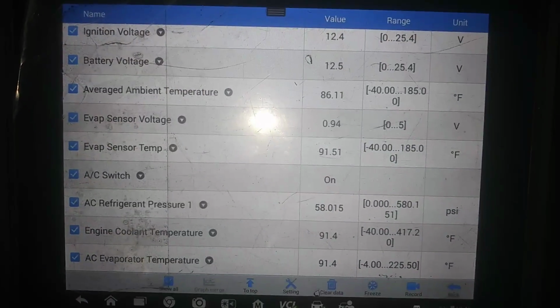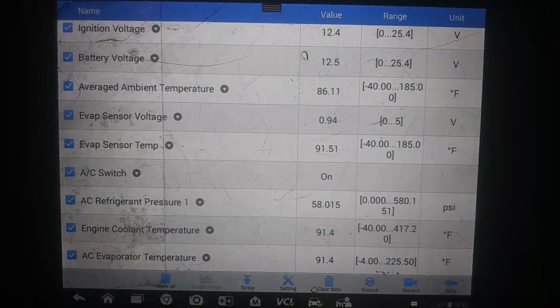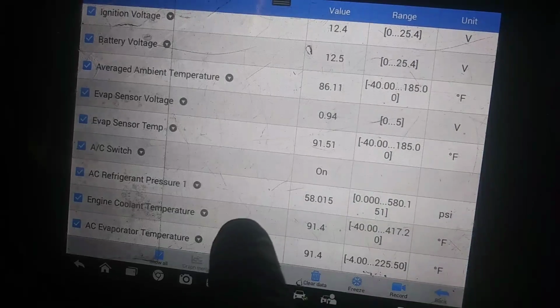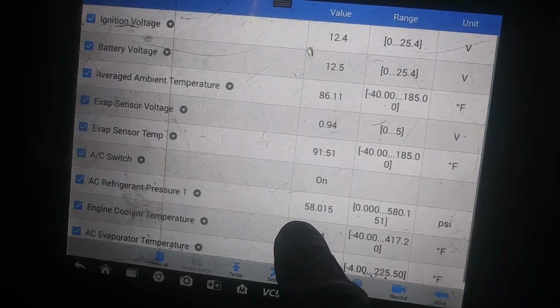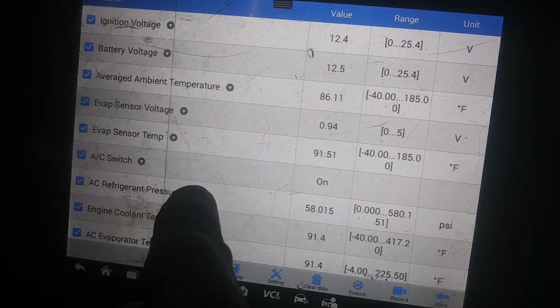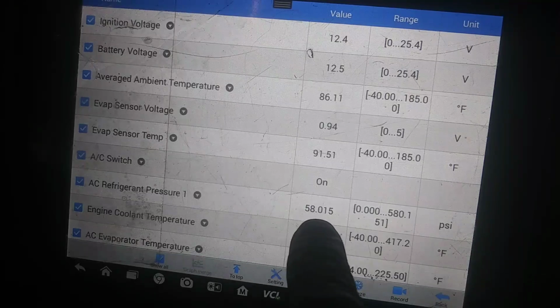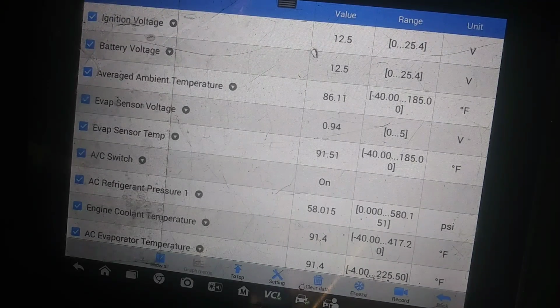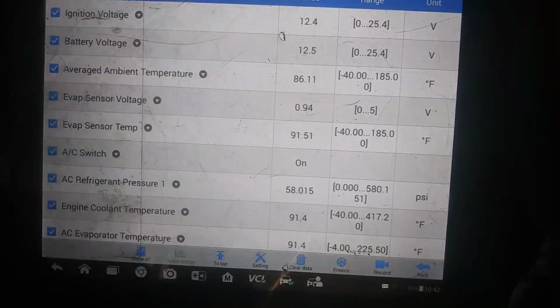All right, let's look at our data. All right, so how much pressure did I put in there? Where's that pressure sensor, refrigerant pressure. I got 58 psi in there, so that's enough to start it up and get it to cycle. So let's do that.